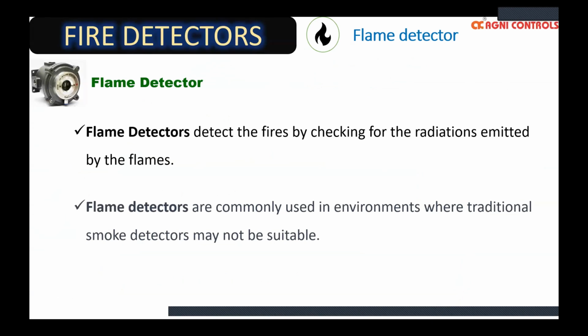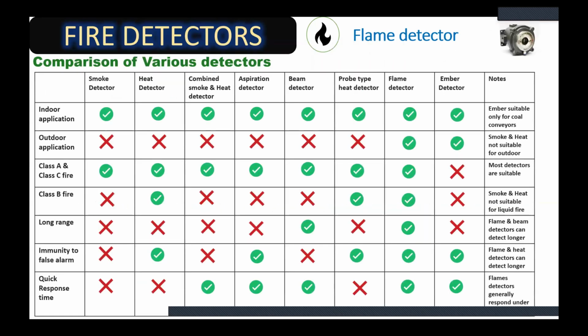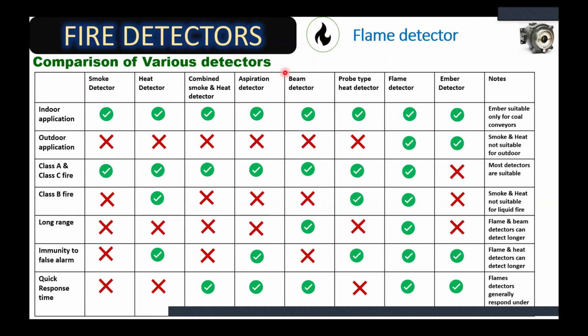So just summarizing, flame detectors detect the fire by checking the radiations emitted by the flames, and flame detectors are commonly used in environments where your traditional detectors are not suitable. So this is a small comparison of various types of detectors. On the first column, I have different kinds of applications like indoor application, outdoor application, class A fire, which is ordinary combustible material, class C fire, which is energized electrical equipment, class B fire, which is flammable liquids and gases, long range detection capability, immunity to false alarms, and the response time.